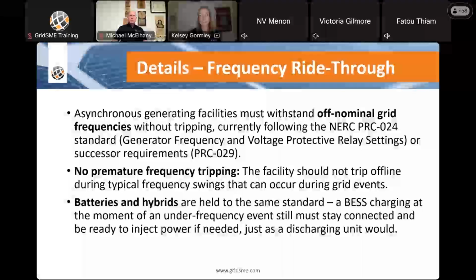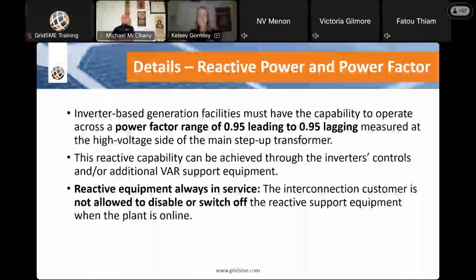All right. So reactive power and power factor, that's the next section we'll talk about in Appendix H. Most of you guys are familiar with this. This is actually also represented in your LGIA. So inverter-based generation facilities have to have the capability to operate across a power factor range of 0.95 leading to 0.95 lagging. And that is measured at the high voltage side of the main step-up transformer.